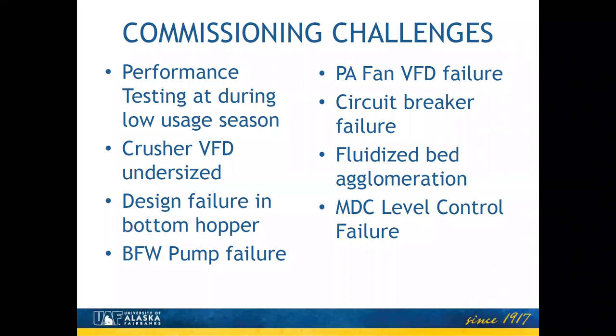Yeah. And so that one's still under investigation, and we're narrowing in on the root cause. We're not 100% sure yet. But after we got past that, we were ready to operate again, and then we had some level controls fail. They failed in a device called the multi-clone dust collector. That's a piece of the back pass of the boiler that collects the particulates out of it and loads them back into the furnace bed, where they can become part of the fluidizing action. And without control of the levels on those, we're not able to operate the boiler successfully. So we're in the process of getting those repaired right now.